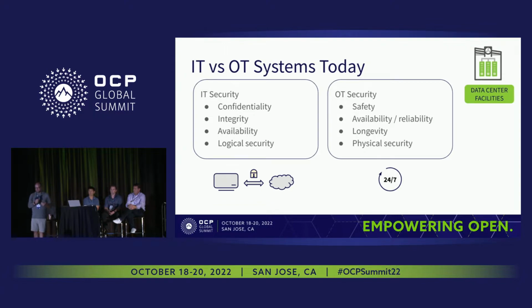OT equipment has traditionally been designed with life safety in mind. A fire suppression system cannot go offline - it has to be operational. There is a life safety event if there's a problem with that, so that has to be a primary design point for those systems.